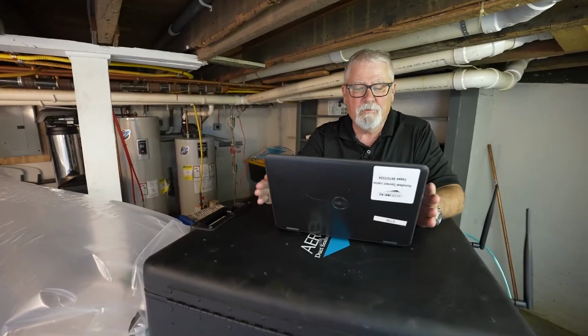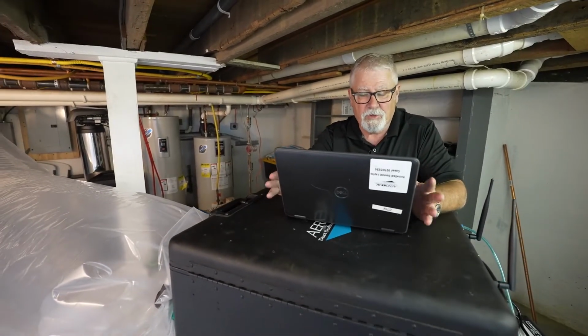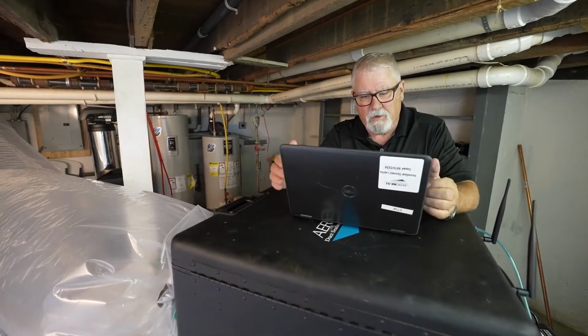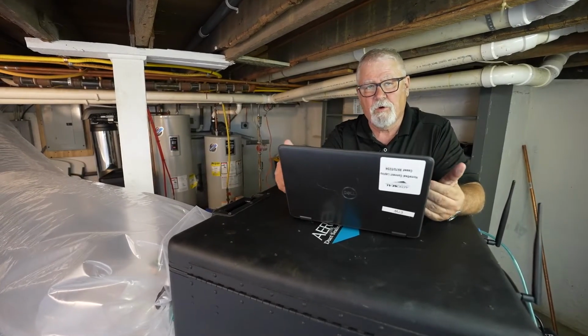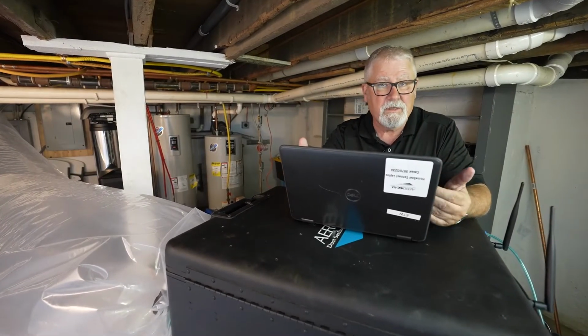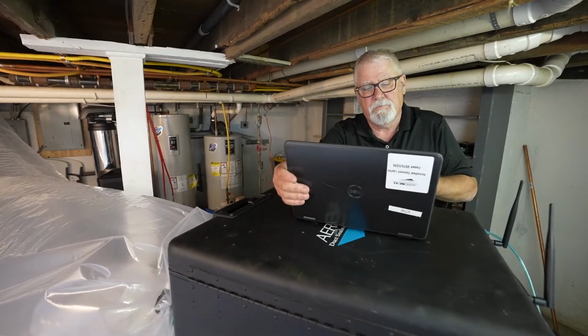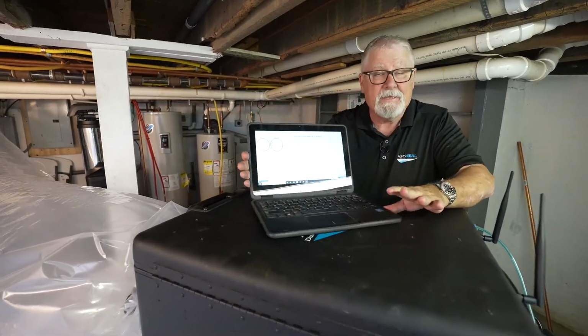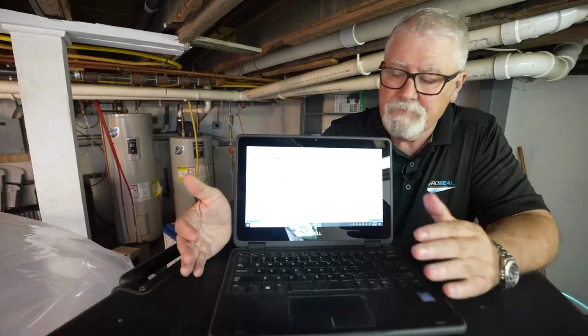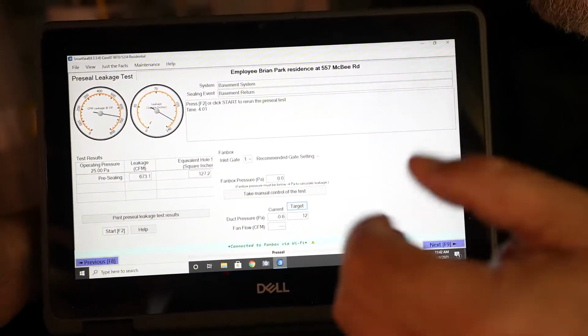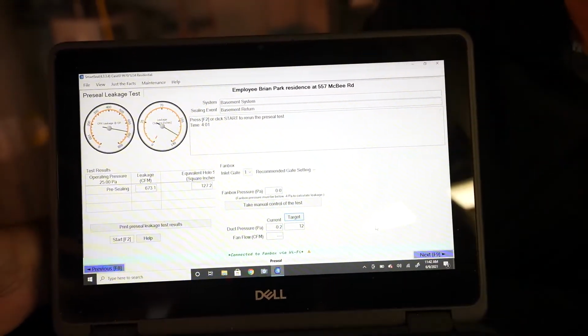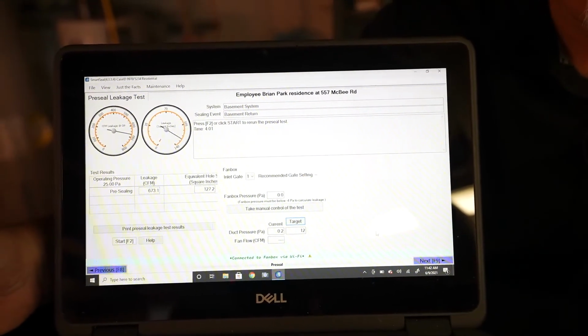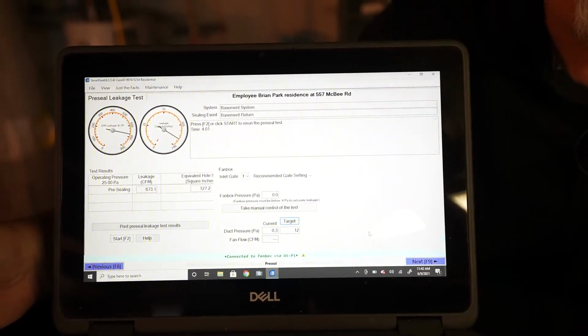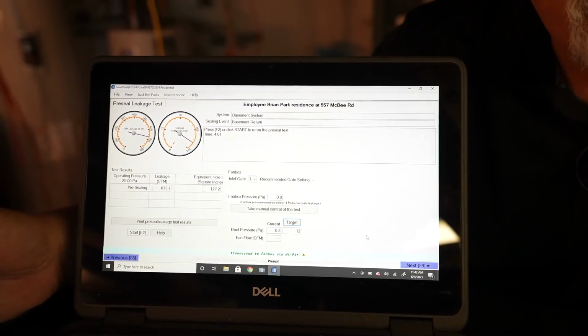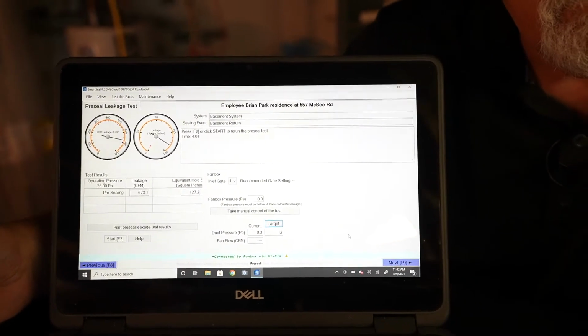So what we've done here is hook up our lay flat and do a test just on the return side, with the equipment blocked off. We want to see how many square inches of holes we're up against that we need to seal up so we can actually do an Aeroseal job. I had to have it all the way open in gate number 1, and I couldn't get a pressure of 25 pascals. The maximum I could get was only 12, and it came up with 673 CFM of leakage. But more importantly to me, I got a 127 square inch hole in this return side.